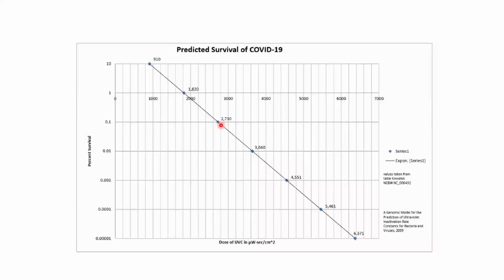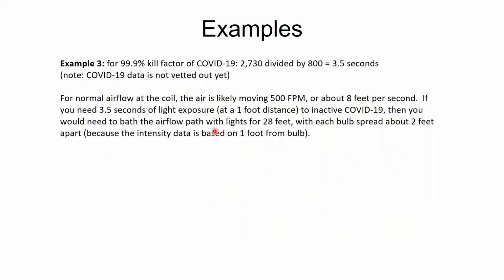So COVID compared to influenza is actually pretty easy for UV to kill. I can kill 99.9% of it with only 2,700 microwatt seconds per square centimeter. All right, doesn't sound that bad. Let's do the math on that guy. Assuming I got the 500 feet per minute by my coil, which is 8 feet per second, I need 3.5 seconds of light shine exposure at a 1 foot distance to inactivate COVID-19. So I would need 28 feet worth of light bulbs spread apart 2 feet from each other. That's like 14 bulbs I need. That's not realistic. So if you're expecting to put UV lights in your HVAC coil and have that kill COVID for your occupants, it's not going to happen.